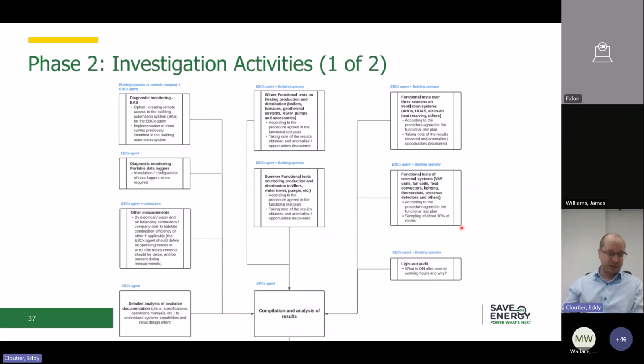To see all the potential deficiencies and EBCx measures, you need to observe the building operating in these different seasons. So the EBCx agent, accompanied by the building operator, will do winter functional tests, for example on boilers, heat pumps, and ventilation systems used for heating the building. They will also do summer functional tests, focusing more energy on chillers, water cooling towers, chilled water pumps, and other such systems.